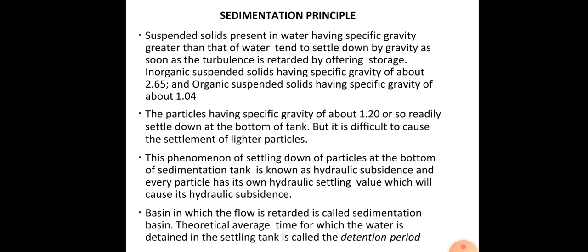The main principle of sedimentation is that the suspended solids present in water, those which have a specific gravity greater than water, will tend to settle under the force of gravity. We can say that all particles which have a specific gravity of 1.2 or above will readily settle down to the bottom of the tank. When it comes to the lighter particles, it is a little difficult, especially very light particles which have specific gravity less than water, and also the colloidal particles. Those cannot be removed by the sedimentation process.